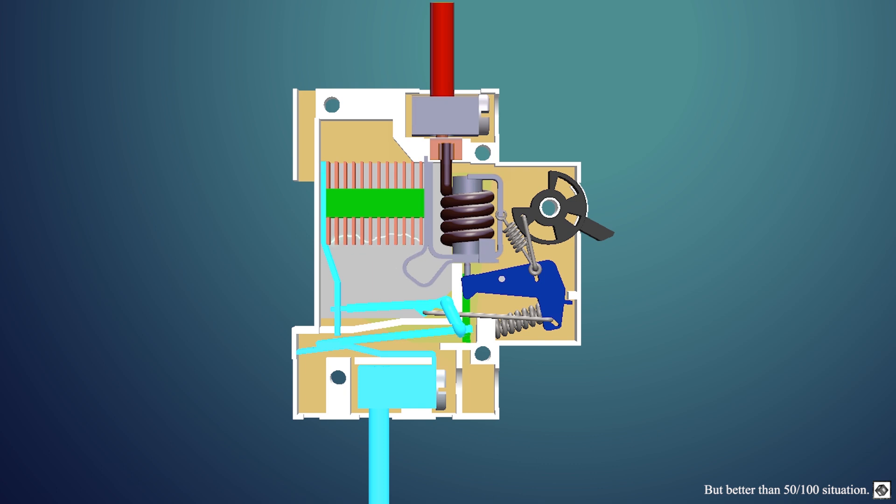This spark can break due to the increased distance between the guides, but if it doesn't break, then the spark is broken into small multiple pieces by the spark divider such that they would not be capable of sustaining the spark for a long time, and it will be extinguished. You may also know that a spark is a plasma and produces a lot of heat.